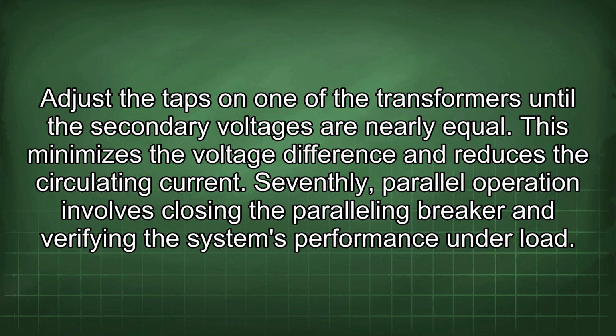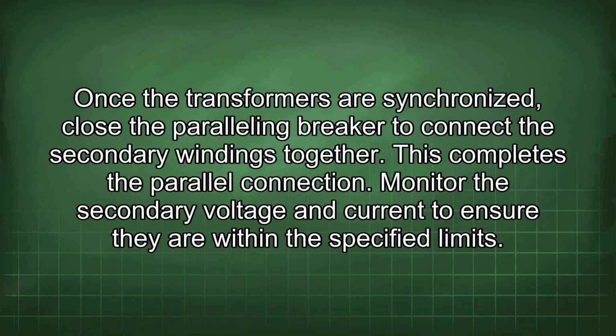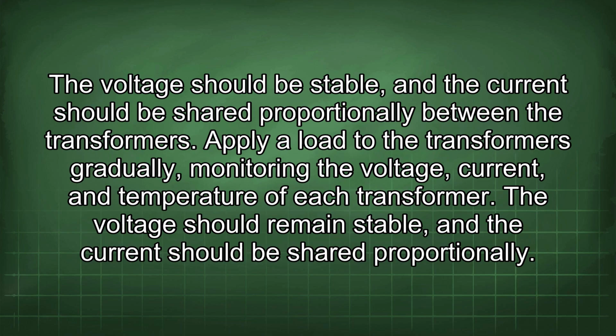Seventhly, parallel operation involves closing the paralleling breaker and verifying the system's performance under a load. Once the transformers are synchronized, close the paralleling breaker to connect the secondary windings together. This completes the parallel connection. Monitor the secondary voltage and current to ensure they are within the specified limits. The voltage should be stable, and the current should be shared proportionally between the transformers.